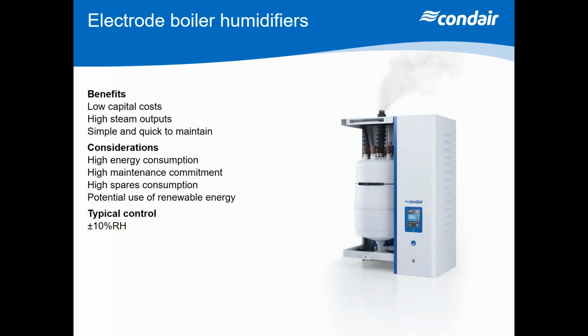So because of the way that it modulates, it will give you plus or minus 10% RH control. So for a comfort application, great. But it will only modulate between 20 and 100% of its output. So in a mid-season application, it may just be on-off control. Still going to give you typically plus or minus 10.